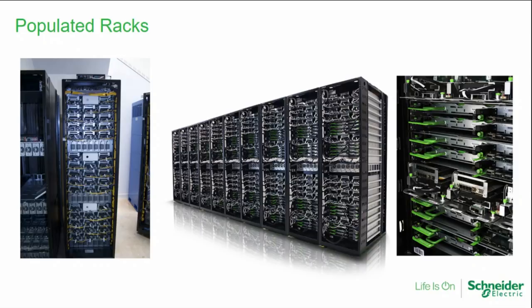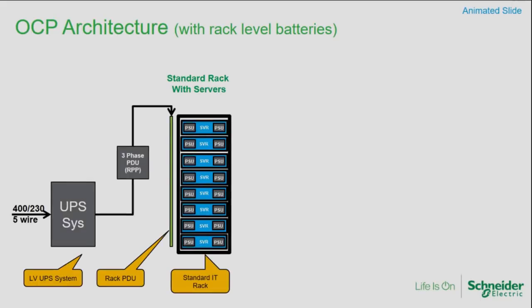Now I have another slide that shows a little bit more of what happens to the infrastructure just upstream of this rack. If you look at a traditional data center with a traditional rack, you're going to have a UPS system, a power distribution unit or PDU or RPP feeding a rack PDU or outlet strip in the rack, and then cords that go to each server which usually has two power supplies within it. Let me define these acronyms: PDU is power distribution unit and RPP is remote power panel, for those not familiar.